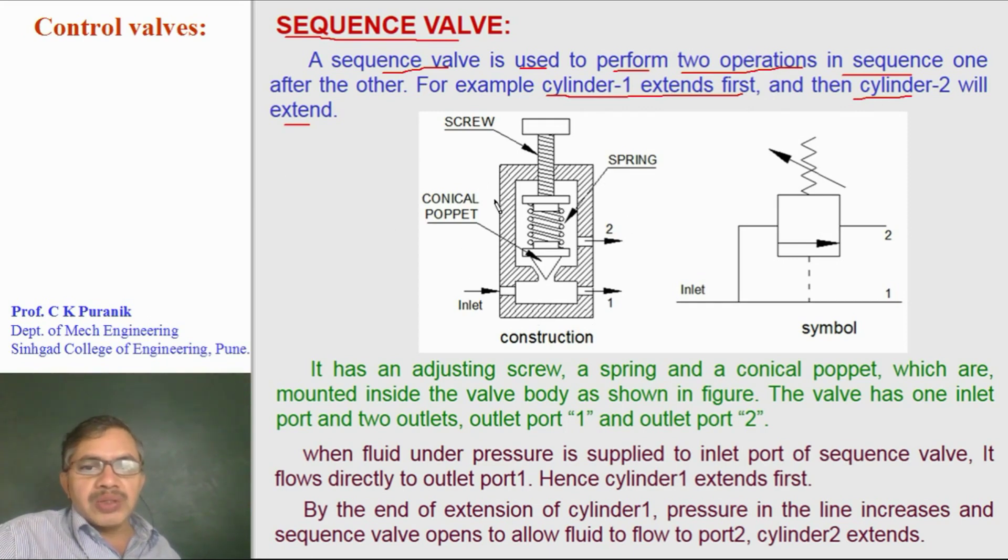Sequence valves are usually used in case of hydraulic systems. Construction is shown in this figure. It has a spring-loaded conical poppet and an adjusting screw. By turning the screw, we can adjust the pressure at which the conical poppet should lift to allow oil to flow to second port.